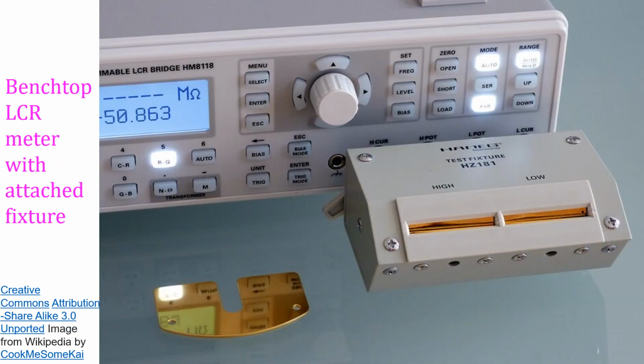The LCR meter measures the voltage across the device under test as well as the current through it. From the ratio of these two, it can determine the magnitude of the impedance. Higher-end devices also measure the phase angle phi between the voltage and current. In an inductor, voltage leads the current by 90 degrees, while in a capacitor, the voltage lags the current by 90 degrees. None of the devices have only one component for the impedance.